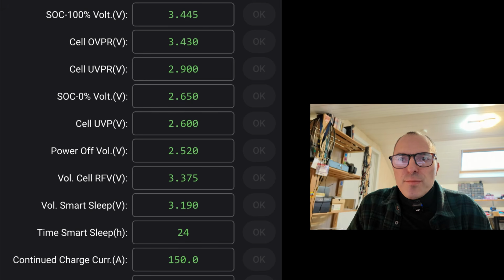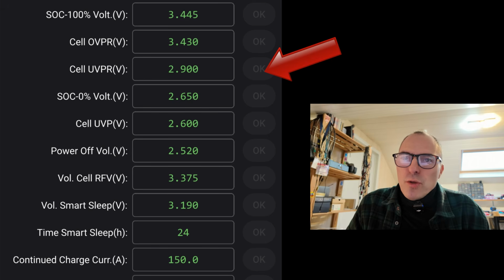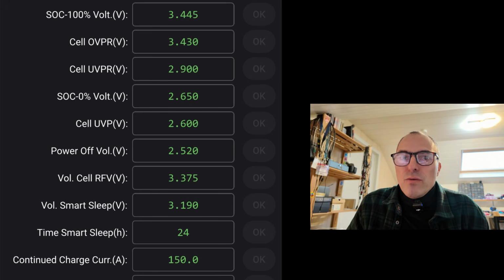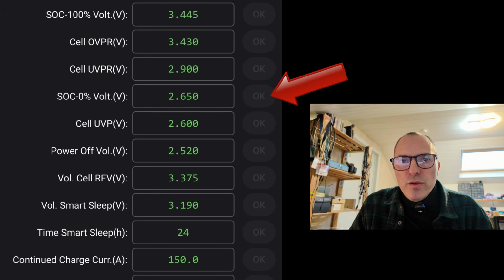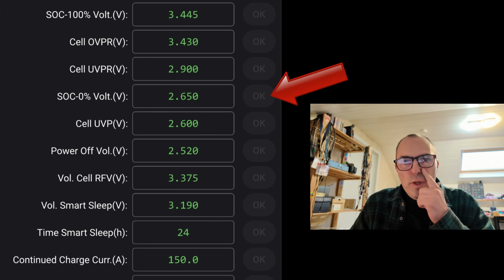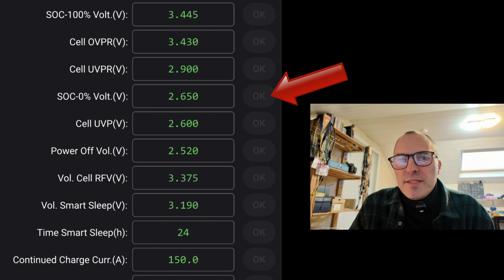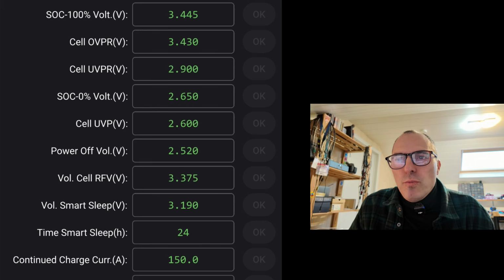Cell under voltage protection recovery. I have set mine to 2.9 volt. Some use a lower voltage, but if you have a high load at 2.6 volt, the voltage will drop again very quickly and battery pack will be disconnected again from the inverter. SOC or state of charge 0%. It's a voltage where your counter will be reset to 0%. I have set my voltage to 2.65 volt.